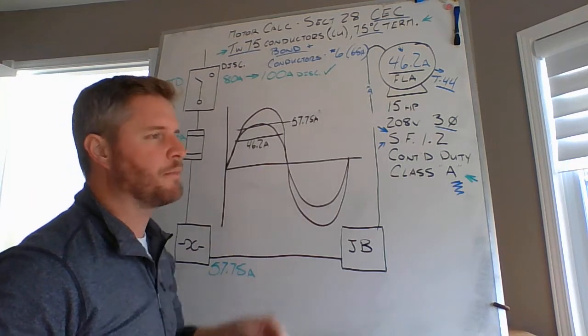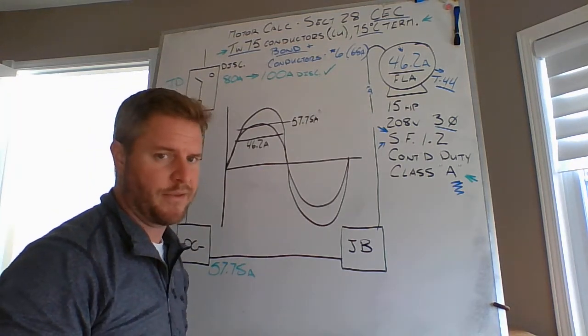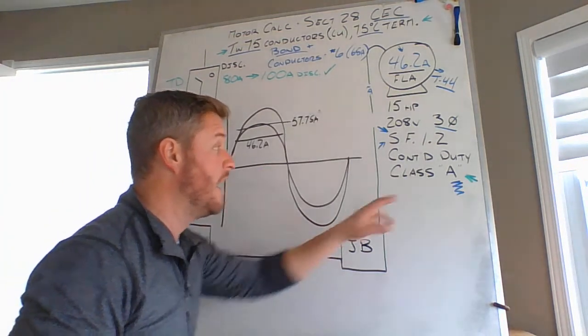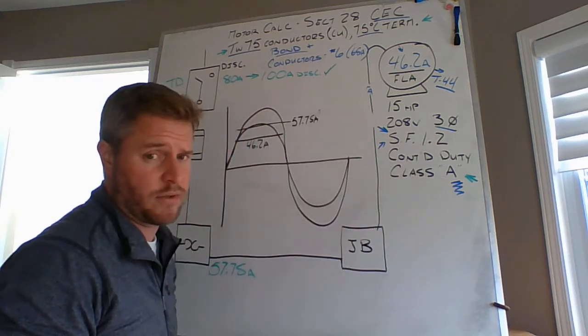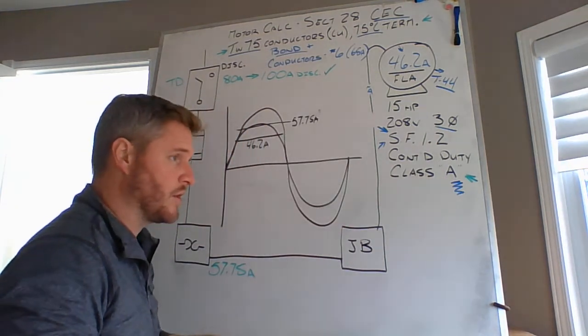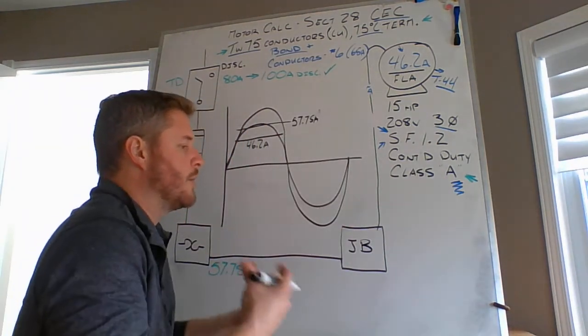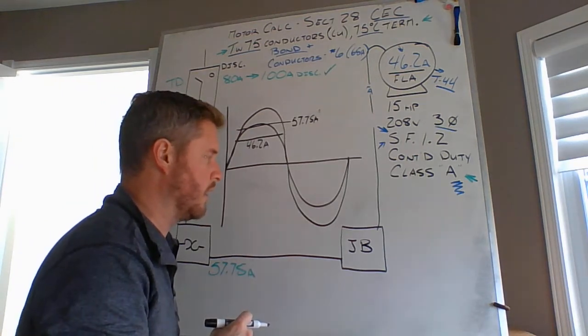So you can draw 57.75 against this 46.2 amp full load current rating of the motor, being at 15 horse, but you're kind of stretching it. The motor is working way too hard, especially for a Class A installation. That means that motor is going to start to create a lot of heat. It's under too much duress. There's too much torque there.